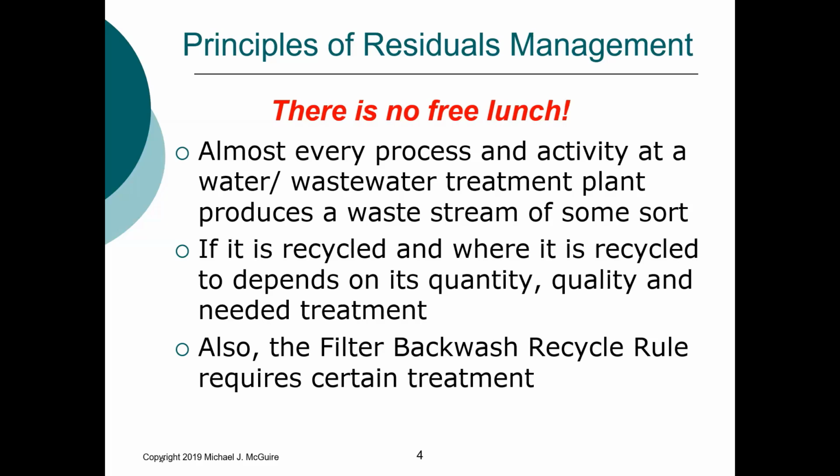You may see that backwash water is recycled. In other cases, it's not. If we're looking at filter backwash, we really have two options. We can recycle it to the headworks of the plant, so before any other treatment is done, or we can discharge it to the sewer. If we discharge it to the sewer, it becomes the wastewater treatment plant's problem, basically.